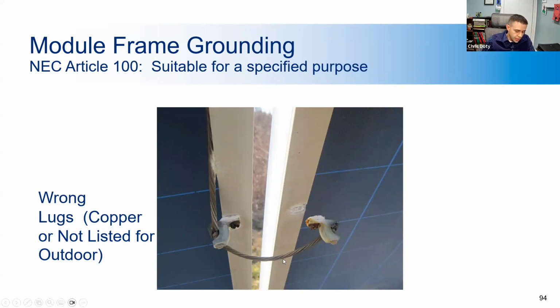This is the ground wire and it's not even connected to this panel, so it's definitely not grounded correctly. And this happened just in the time between the build and interconnection and the quality assurance inspection. So by that point, which is probably months, the screw had already corroded to a point where it broke away from the panel frame. So this one is likely not far behind.